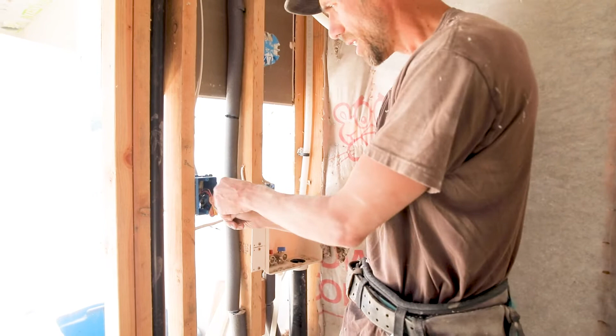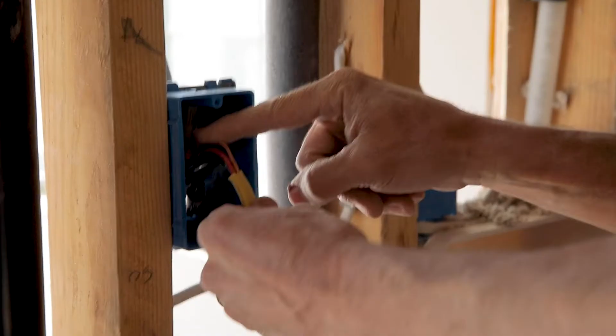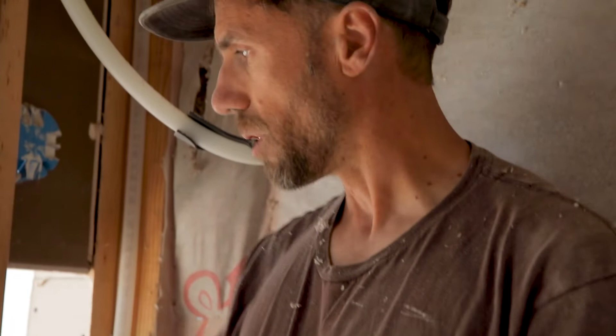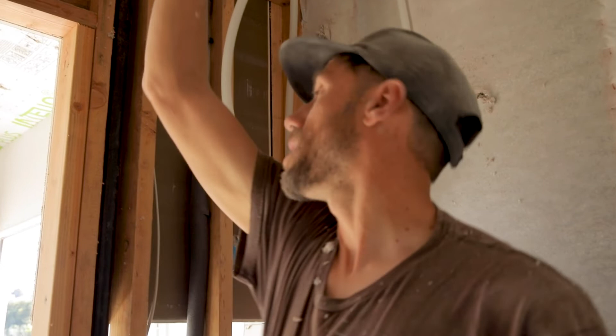And it comes into here, and it's one of these black wires in here. And the other black wire that you see runs up through one of these wires, and it goes to our light right there. So that black wire there is the one that's here, and those two black wires are going to connect. When you flip that switch, those two black wires connect. And so hot is able to go from our panel now through the switch up to the light. It's going to go through the light bulb, and then it's going to hit the white wire and return on the white. So it's going to return back the same way it came. Now all of our white wires are tied together here, so they're not switched. Only the hots are switched. So it's going to go through that white neutral wire, and it's going to go back the same way it came.